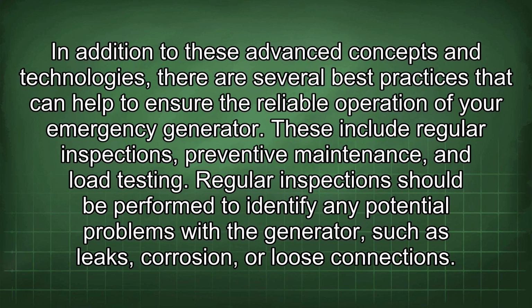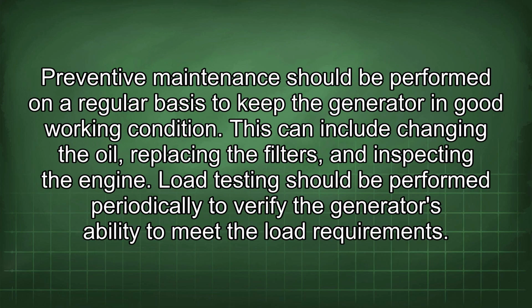In addition to these advanced concepts and technologies, there are several best practices that can help to ensure the reliable operation of your emergency generator. These include regular inspections, preventive maintenance, and load testing. Regular inspections should be performed to identify any potential problems with the generator, such as leaks, corrosion, or loose connections. Preventive maintenance should be performed on a regular basis to keep the generator in good working condition.